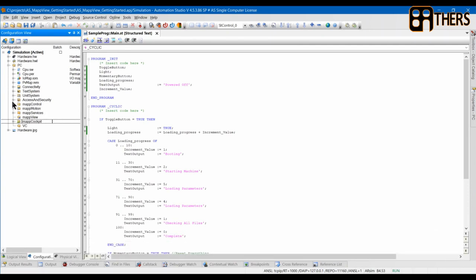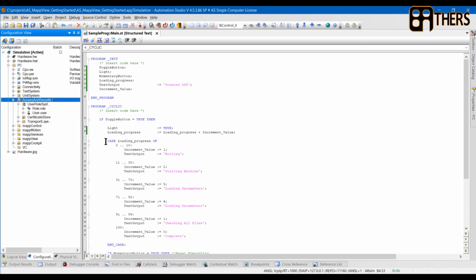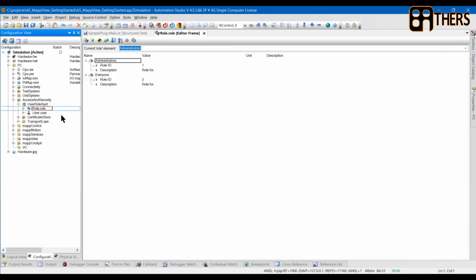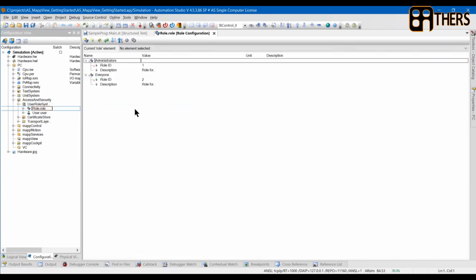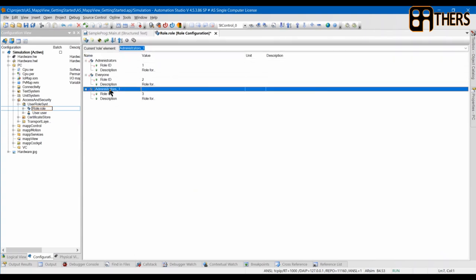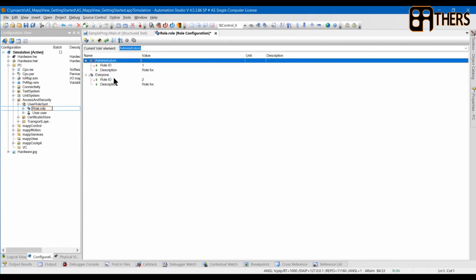In the configuration file, we'll first go to Access and Security because mapp View communicates with the PLC via OPC UA, so we have to set up our OPC UA system first. We'll go into Access and Security, then into Roles. These are the two default roles. You can click the button to add a new role, but we don't need that now — we'll just leave it as Administrator and Everyone.